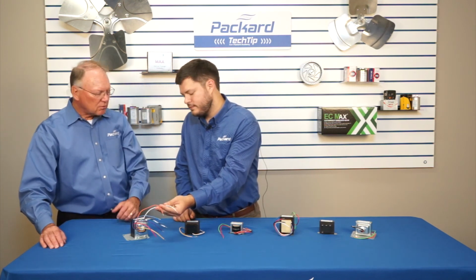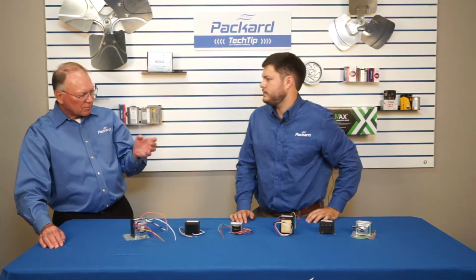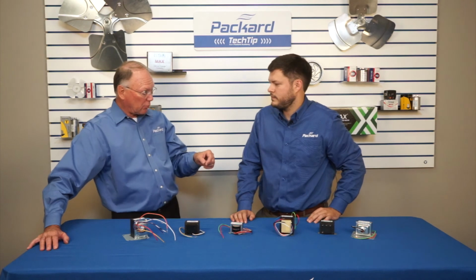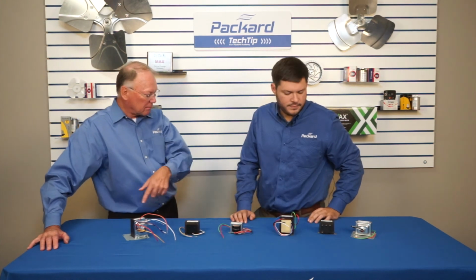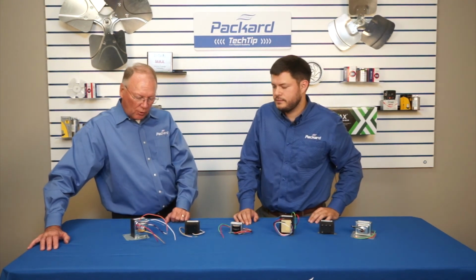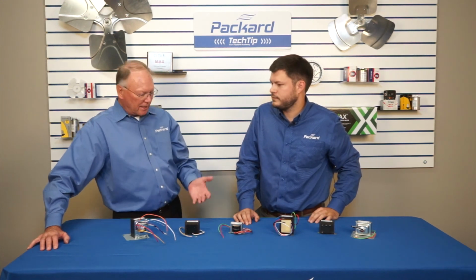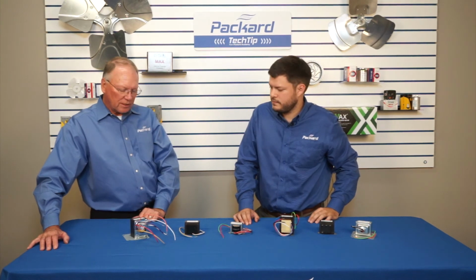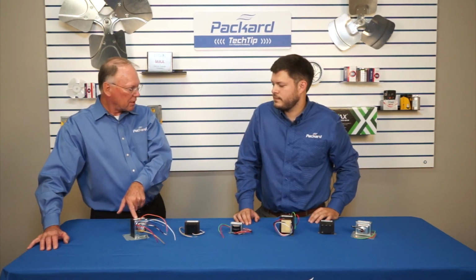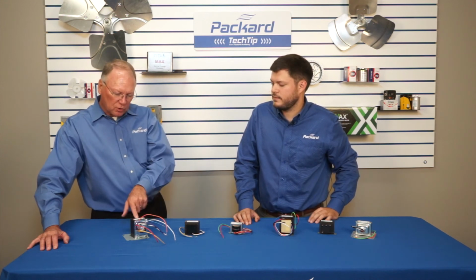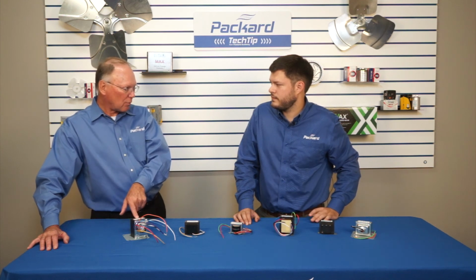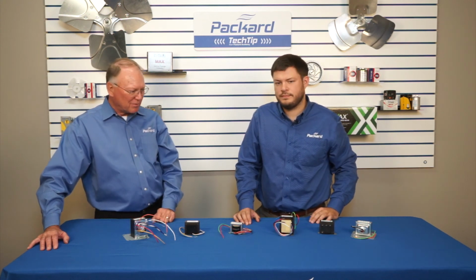So with a transformer, I have two different coils in there, a primary coil and a secondary coil, and the ratings for those coils are shown on the nameplates of each of the transformers. Absolutely. Your nameplate will always indicate which terminals you need to use for both primary and secondary. So I just select the primary, my source voltage, and my secondary voltage, and connect it according to the colors shown on the nameplate. And then I can apply up to the VA rating shown on the transformer, and that transformer will be able to power those particular devices up to that. That's correct. Great. You've made it a lot easier. I hope it helps out.